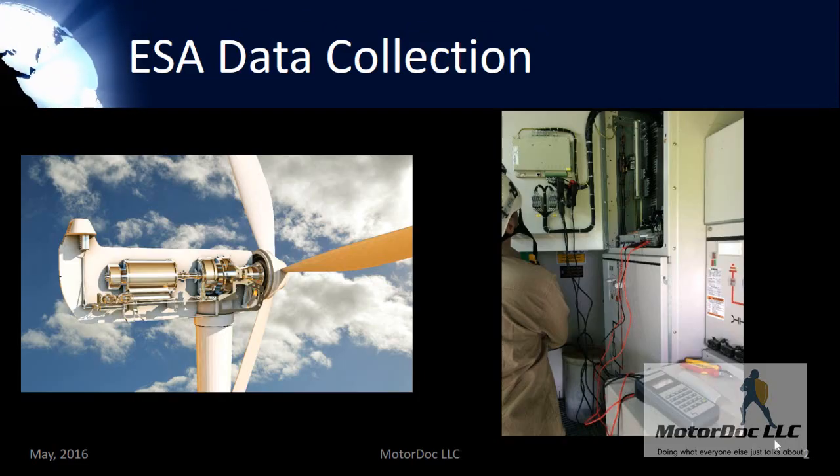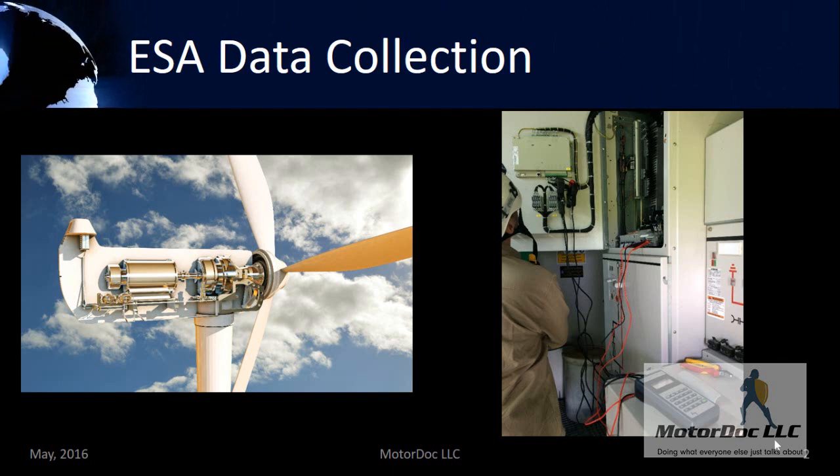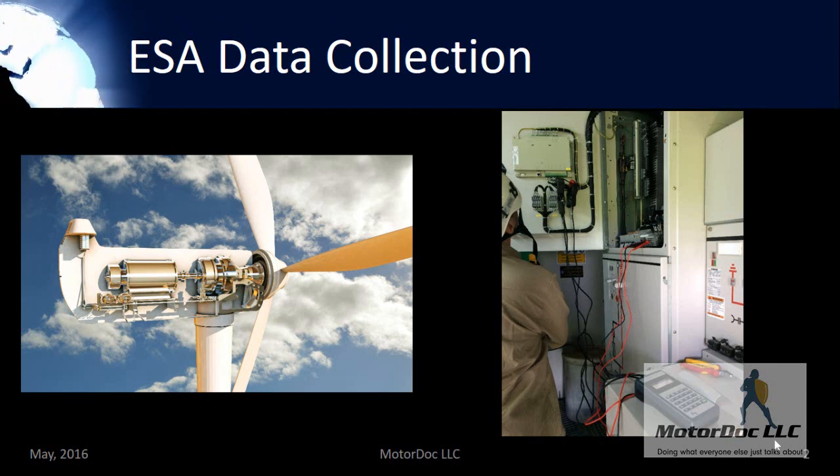The key is data collection. There are some wind generators where you cannot collect the data from the base of the tower — those are the ones that have transformers at the top of the tower. There are solutions in which you can drop down cables with the CTs and PTs attached. CTs and PTs have to be dropped down. Certain systems also have CTs and PTs at the base of the tower, such as the one on the right — a 12.4 kV wind generator — where we are taking data off of the CTs and PTs in the cabinet. There are plugs available such that you can access the data externally to the tower, though those would have to be permanently mounted.